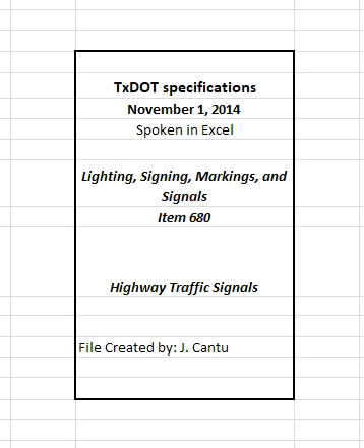3.1.8 Test period. Operate completed traffic signal installations continuously for at least 30 days in a satisfactory manner. If any contractor furnished equipment fails during the 30-day test period, repair or replace that equipment. This repair or replacement, except lamp replacement, will start a new 30-day test period.